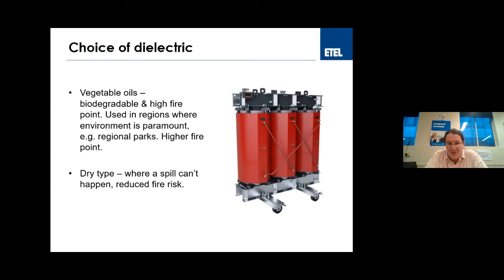There are also the dry types which are coming in - more like the cast resin shown on the right here. This has no fluid; it's a completely solid insulation structure. The great thing about these is that with no fluid, there's no possibility of spills or leaks. When we think about fire safety, one great thing about cast resin is there's no danger of mineral oil leaking onto the floor, and if there's a fire within the plant caused by something else, there's no danger of the oil catching fire too. With this solid insulation, the outside can char - if it's really in the fire, the outside surface will blacken, but the insulation won't actually catch fire. So that's great for infrastructure where we're really worried about safety.